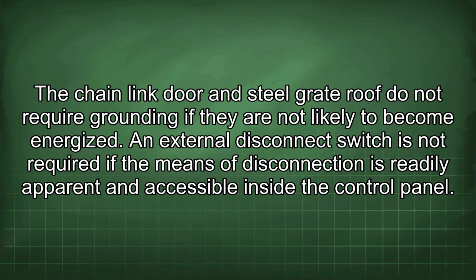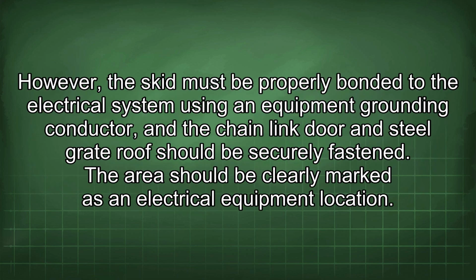An external disconnect switch is not required if the means of disconnection is readily apparent and accessible inside the control panel. However, the skid must be properly bonded to the electrical system using an equipment grounding conductor, and the chain-link door and steel grate roof should be securely fastened. The area should be clearly marked as an electrical equipment location.